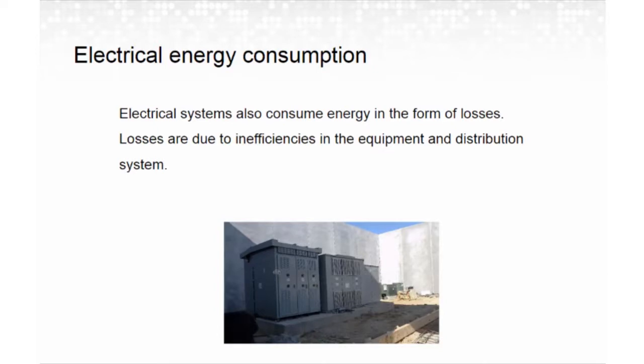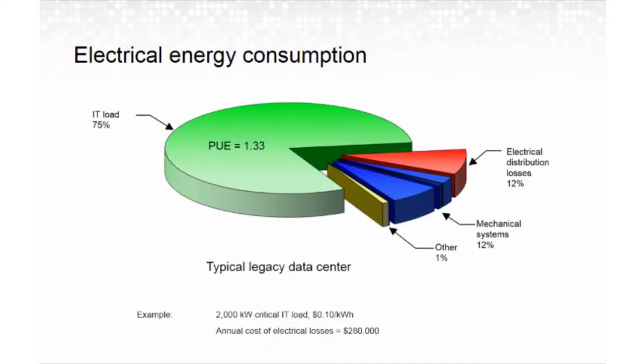The electrical systems also consume energy in the form of losses. So losses are basically due to inefficiencies of the equipment and the distribution system. When you look at facilities that consume a lot of power, like a data center, you can tell by the graph here that the electrical distribution losses equal about 12% of the total energy consumption for the facility. This one in particular is a 2,000 kilowatt data center. You can see the mechanical systems have been made more efficient to get that piece down, but there's still a 12% loss in just the electrical systems itself.